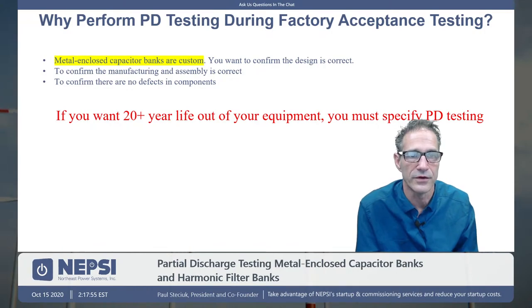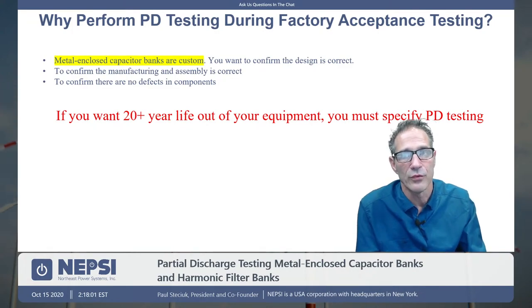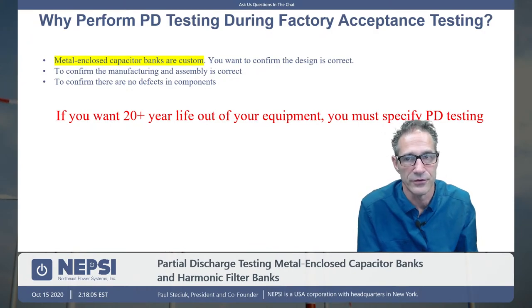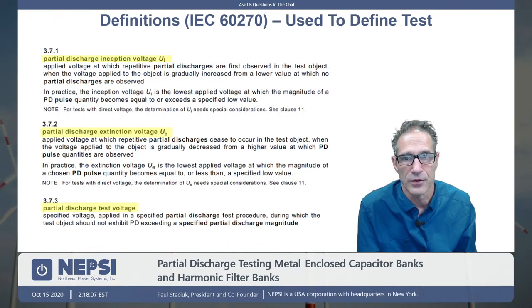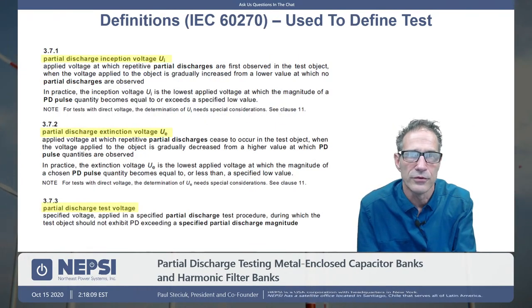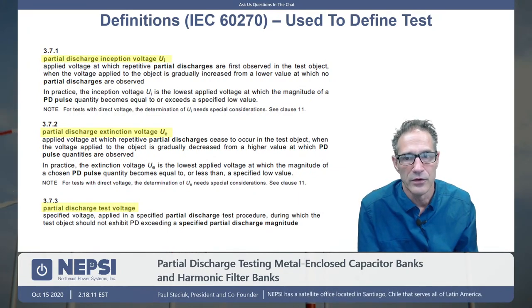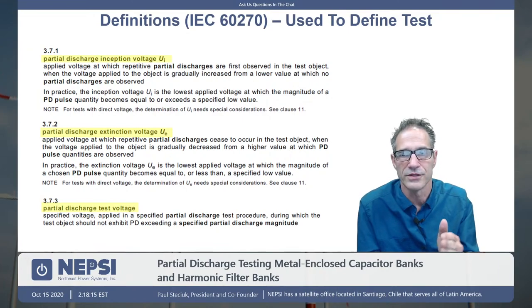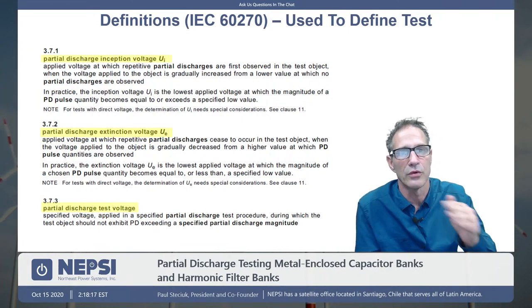All those medium voltage devices that rely upon solid insulation for their impulse rating. So if you want to have 20-year life, make sure you specify partial discharge testing in your equipment. So we're going to just talk about a couple terms that you often see, and all I do is take snippets from the standards. One is called a partial discharge inception voltage, and this is where corona occurs.